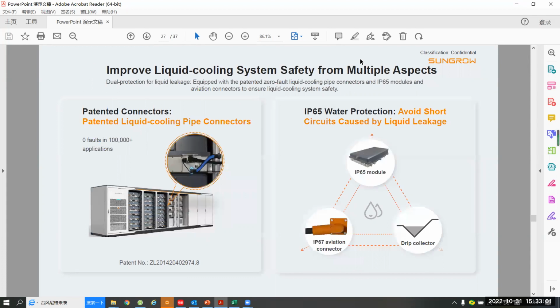Okay, another important point of the system safety protection is the IP level. Because we know the PowerTitan product uses a liquid cooling solution, the most important thing is how to avoid liquid leakage. For this purpose, the first design is that the PowerTitan system uses patented connectors. It is the patented liquid cooling pipe connectors. These connectors have more than 100,000 applications with 0 faults. So it is reliable enough.